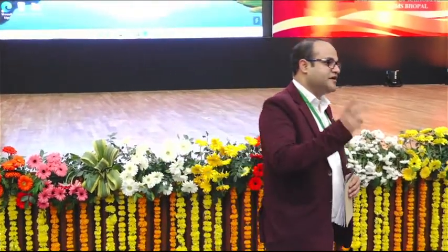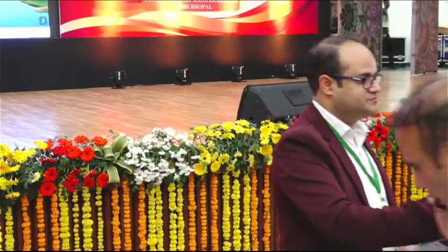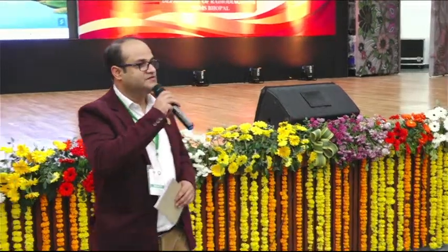The difference between MRI compatible and MRI conditional. MR compatible and MR conditional are two different phenomena. MR compatible is considered to be the safest option, completely safe for a patient to undergo an MR scan. If a patient has any implant and it is MRI compatible, then it is totally safe to conduct an MRI scan.